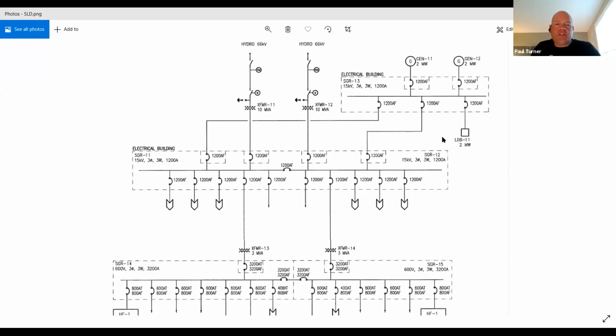Yeah, during the pre-commissioning, you're going to want to check that breakers can be racked in and out, that any remote operation or control from the PLC or HMI systems can control each of the breakers, and that you're getting the correct statuses of each of the breakers back on the HMI system. You're going to want to verify any of the interlocks to confirm that when one breaker is closed, a particular breaker is open, and that's critically important from a safety perspective, that all those interlocks are checked in advance. All of these functionality checks, you're going to want to confirm prior to applying 15 kV to that bus, so that you know that the system is going to function correctly before you have high voltage applied to the main bus of the switchgear.